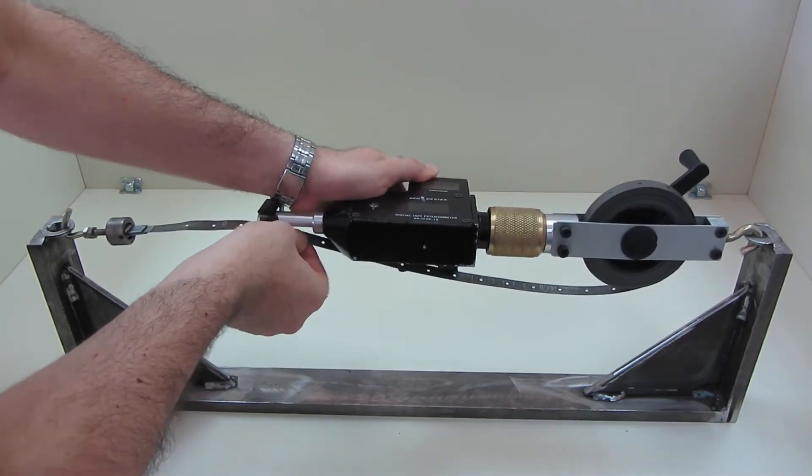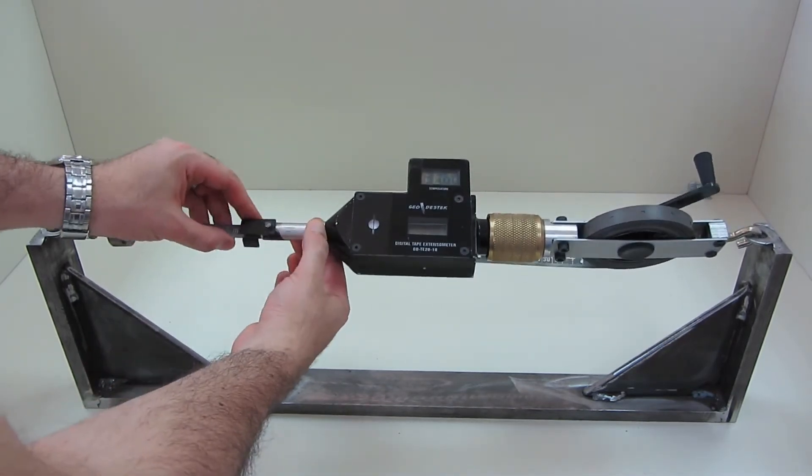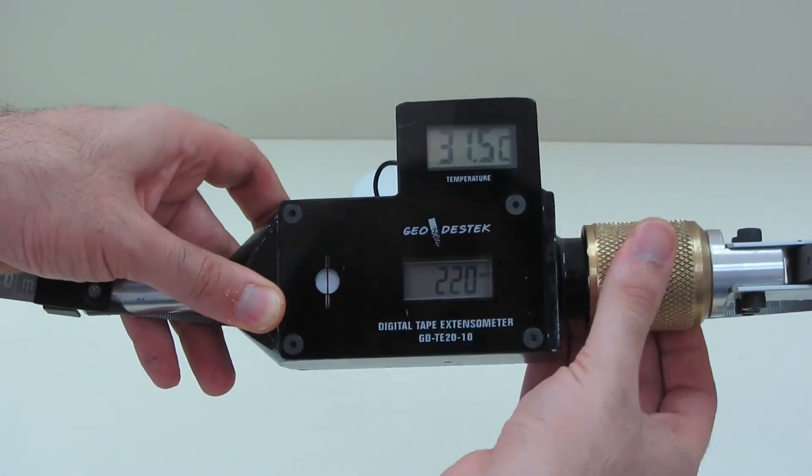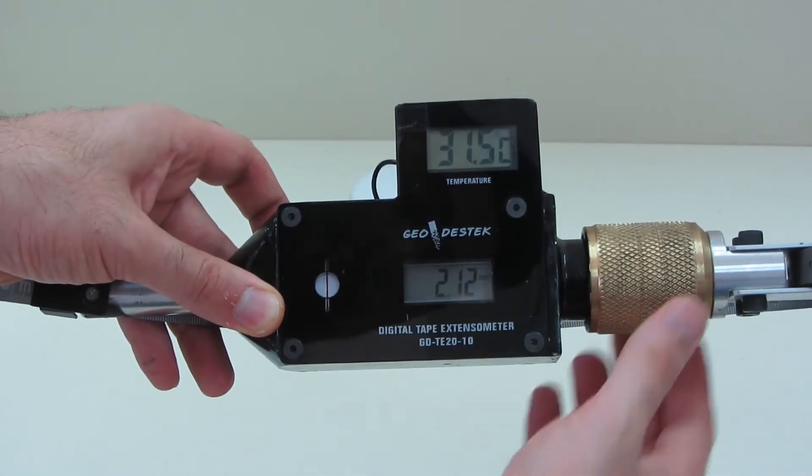By utilizing the pretensioning screw, the tape is tensioned to a standardized tightness that is optically confirmed. The opening between two reference points can be measured and recorded.